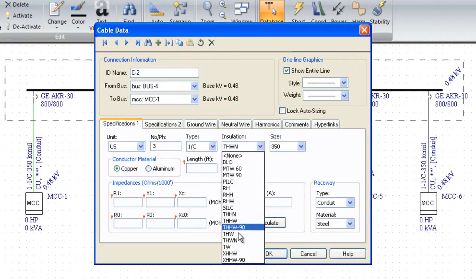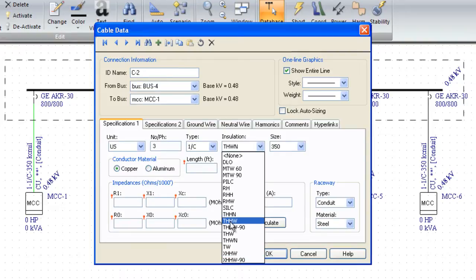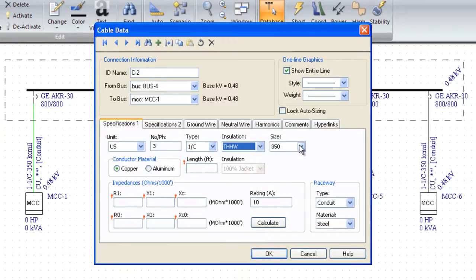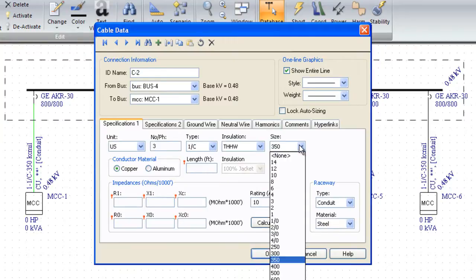Insulation types: we model the XH series or the cross-linked polyethylenes, the thermoplastics, the THs, the heat resistant rubbers or RHs, even the old paper insulated lead conductors if you've got a really old facility. Any size from 2000 KCMIL to 14 AWG.